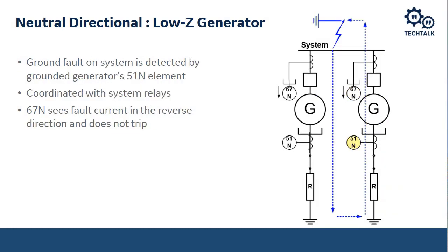If we have a fault out in the system, the ground fault is detected by the 51 element, so if we do have a fault in the system, we still want to trip our generator if that fault is not cleared in time. We don't want to cause damage to our generator, but we also want to allow the system protection to trip that fault first. So we coordinate with this 51N for external ground faults. However, if we have an internal ground fault, the 67N element, which is looking only in towards the generator, will trip for that fault, and it will trip for only the fault in that particular generator. So we're able to locate exactly where the fault is and isolate that piece of equipment only. Whereas with the 51N, we'd probably have to trip both generators for a ground fault in either one of them.